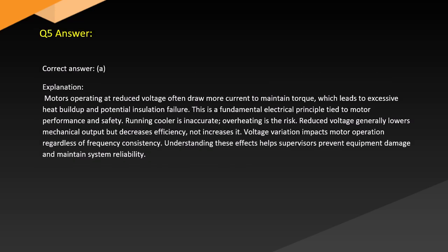Answer. Correct answer, A. Explanation. Motors operating at reduced voltage often draw more current to maintain torque, which leads to excessive heat buildup and potential insulation failure. This is a fundamental electrical principle tied to motor performance and safety. Running cooler is inaccurate. Overheating is the risk.